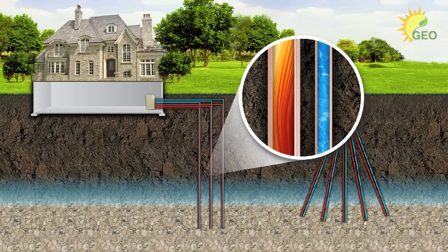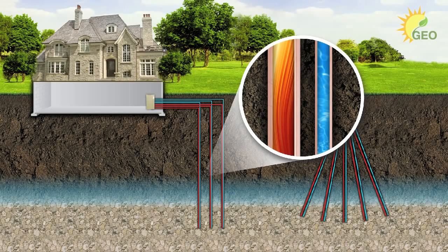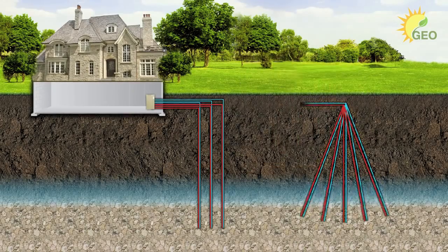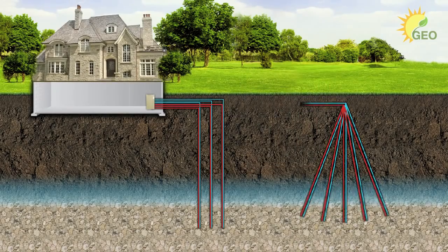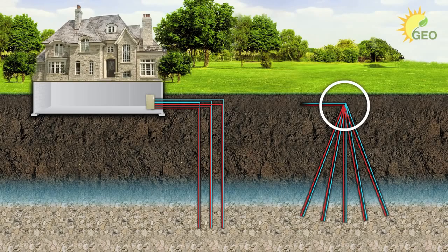Envision each borehole as a 7-foot diameter cylinder that uses this area to gather the Earth's energy. When ground space is a concern, a teepee style or slant configuration can be used to reduce the area needed for drilling. Notice the reduced surface area needed at the top of the boreholes.